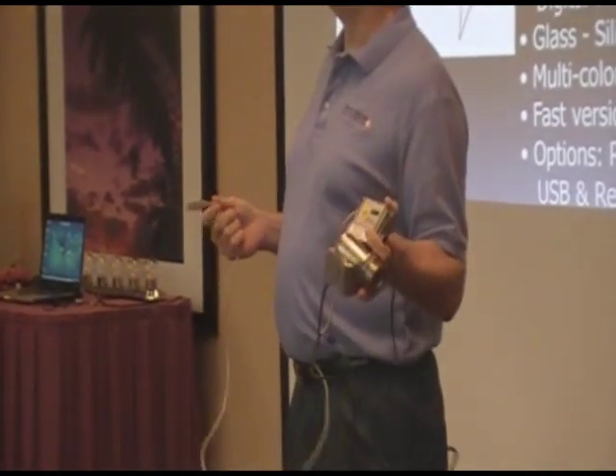Here you have all the outputs: J, K thermocouple, voltage outputs, milliamp outputs straight from this box — all switchable. This particular one has a USB board in there, so it's powered by your computer.